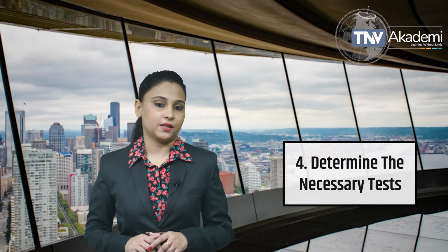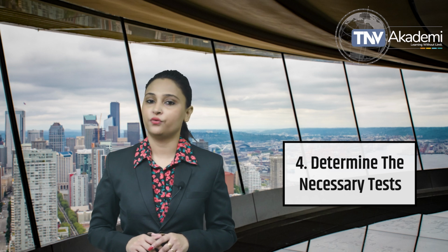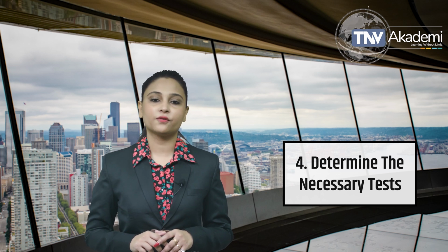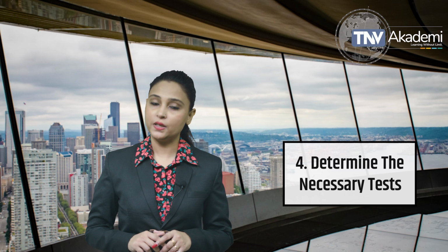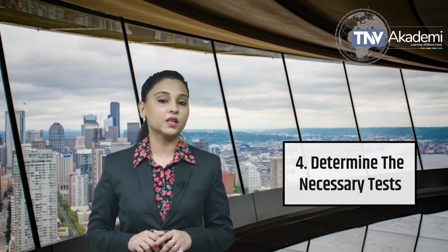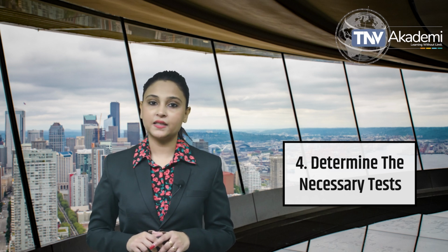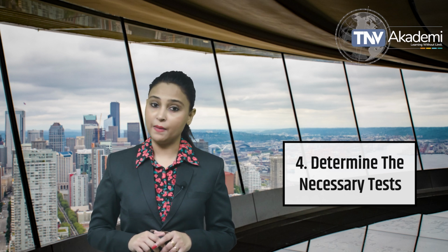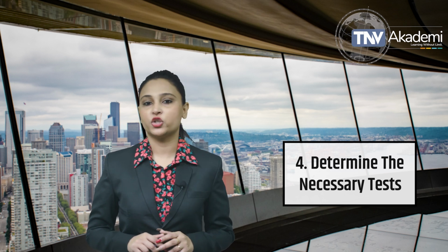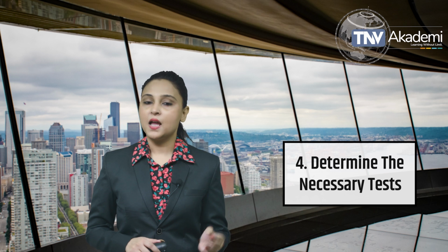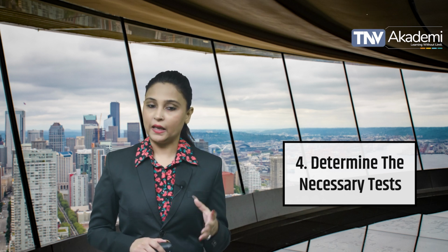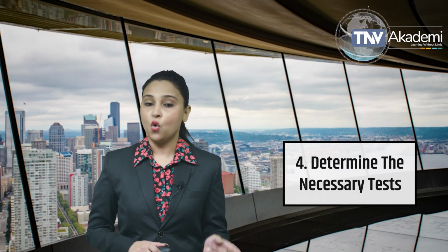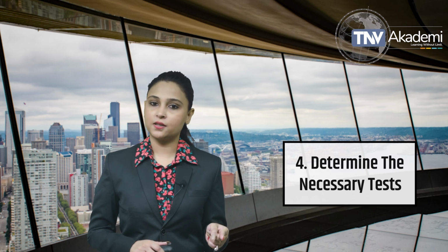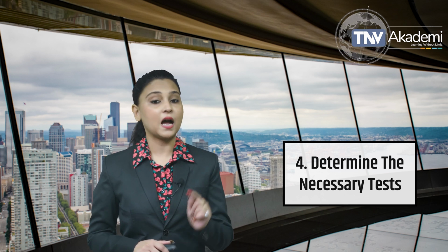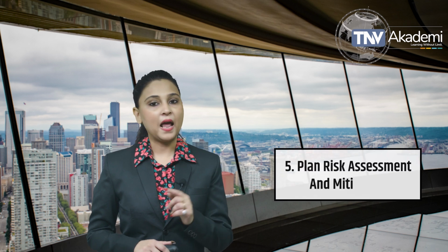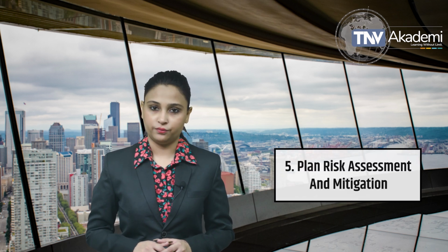Determine the necessary tests. Once hazards are identified, select the appropriate tests from the ISO 10993 series. These tests may include in vitro, lab-based, and in vivo animal-based or clinical methods to assess specific biological interactions. For example, cytotoxicity tests evaluate if materials harm cell health, while systemic toxicity tests examine effects when materials are absorbed by the body. Plan risk assessment and mitigation.